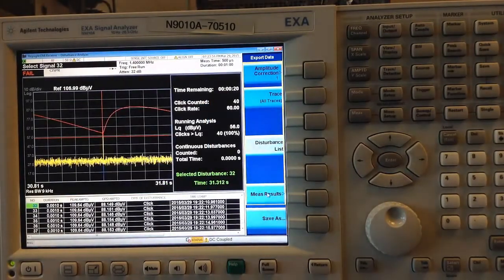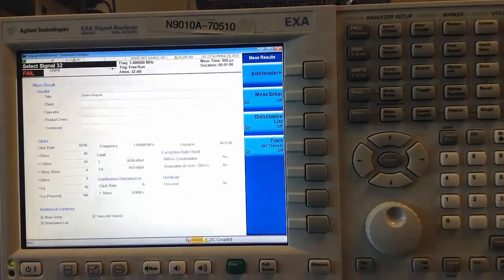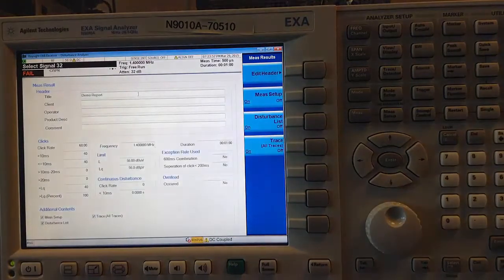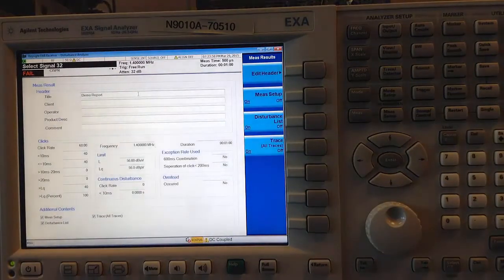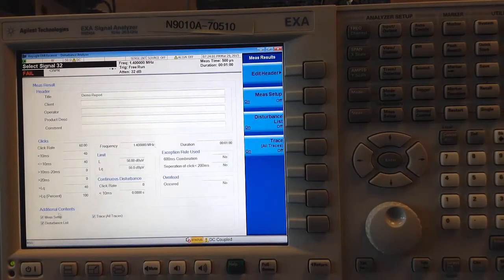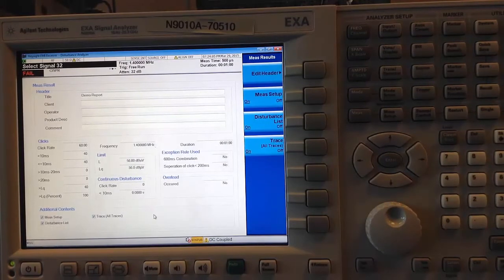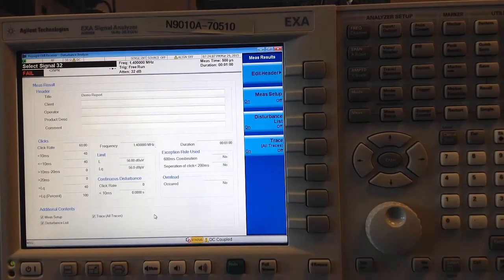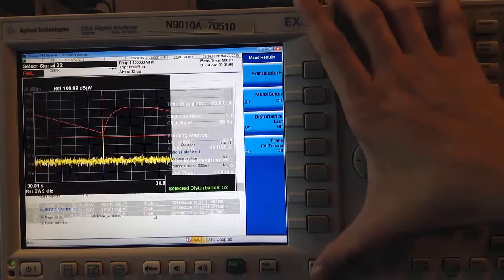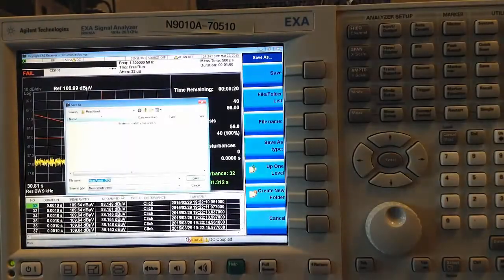And I can go to Measure Results and enter a header as well as save the measure setup, the Disturbance List, and all of the traces together in a complete measurement report. This would be saved in HTML format.